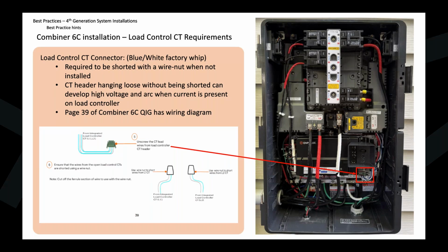Be careful when you're removing it. Remove that header of that load controller CT, and then cap those individually, so that if there happens to be current on that load controller, it doesn't arc and potentially hurt or shock someone. So when you are wiring consumption CTs in, make sure you pull that header off of the load control header and wire nut those for safety.